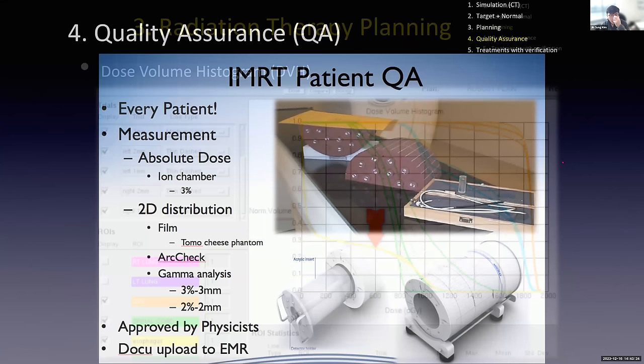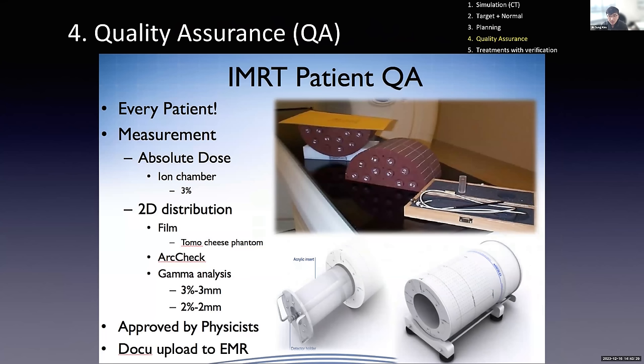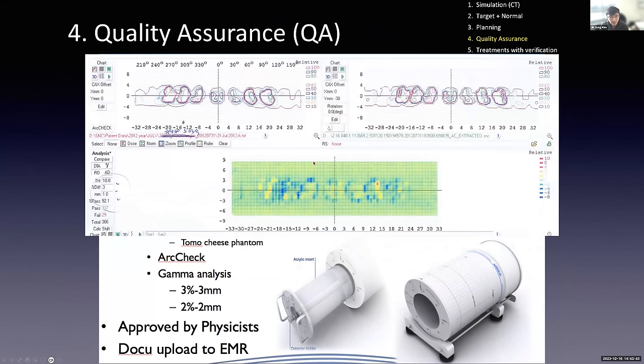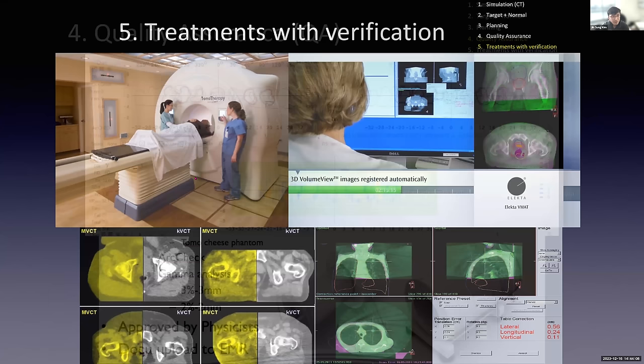Step four is quality assurance. We use film or an ion chamber system to measure and compare the treatment planning against actual measurement. We perform gamma analysis — comparing the simulation versus measurement result — and after checking against some threshold, we can proceed with treatment.